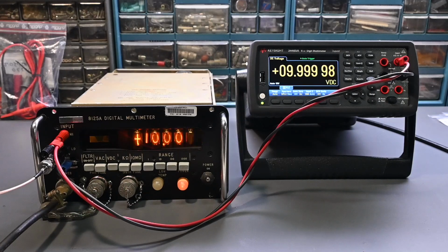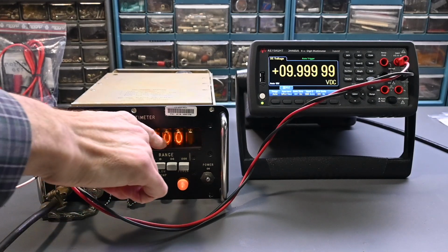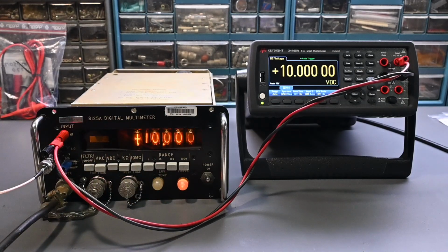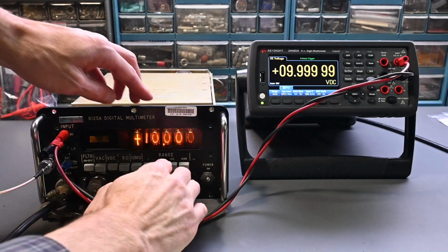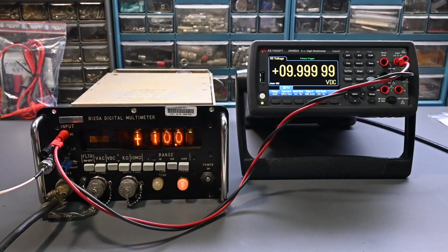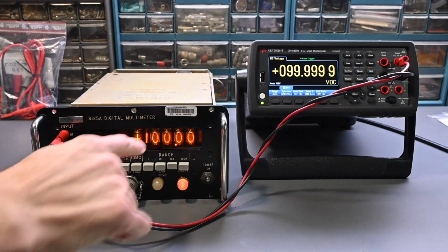Takes a little bit of time here to dial in. Right there. So right at 10 volts, and no problems, sitting right at 10 volts there. And if I go to the 100 volt range, and then I step this up here to 100 volts, it needs to settle in. So right there, looking very close, right on 100 volts, and no problems.